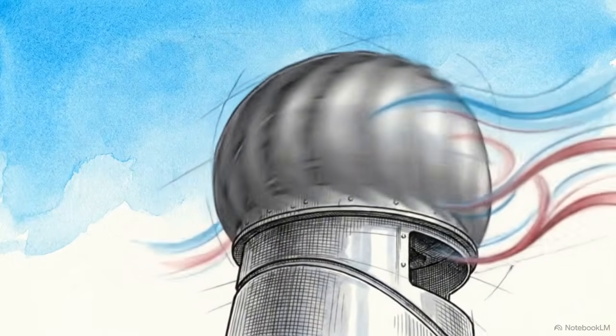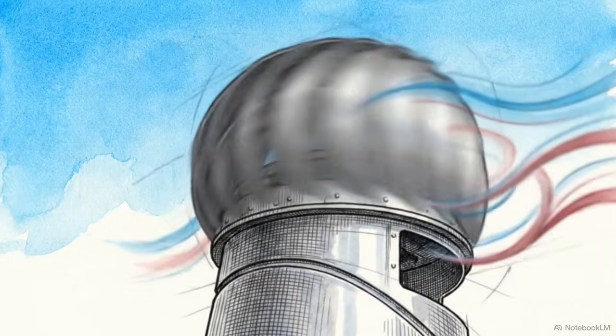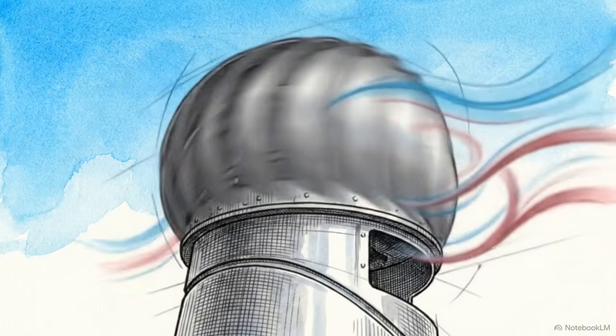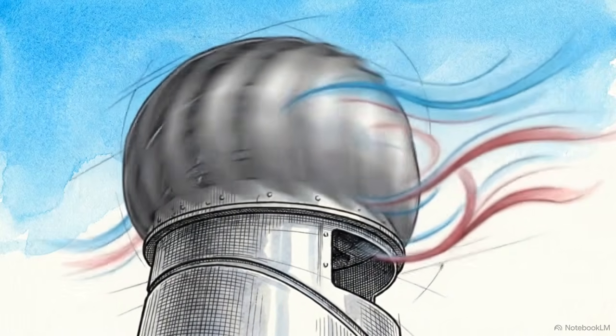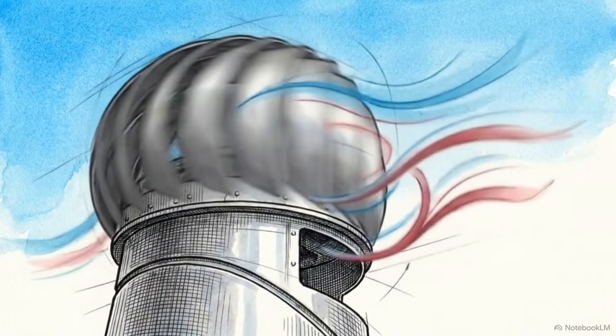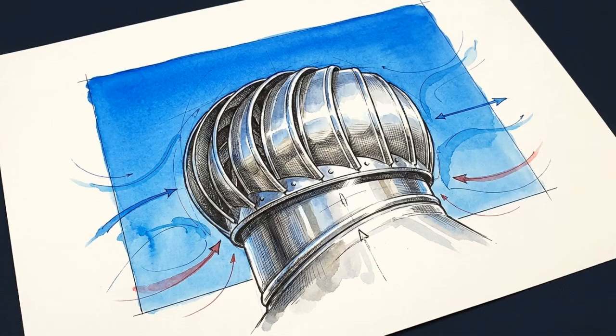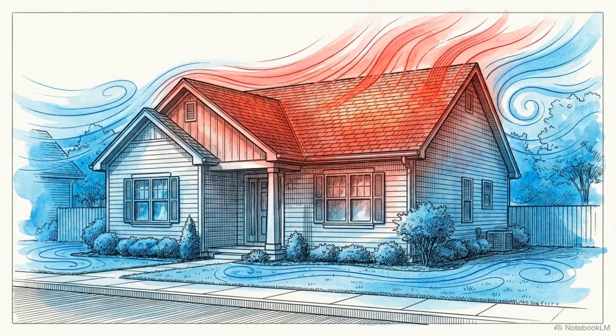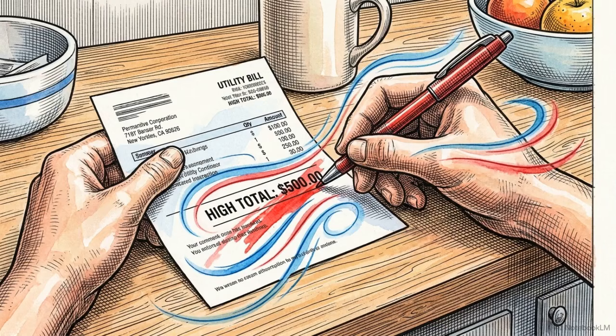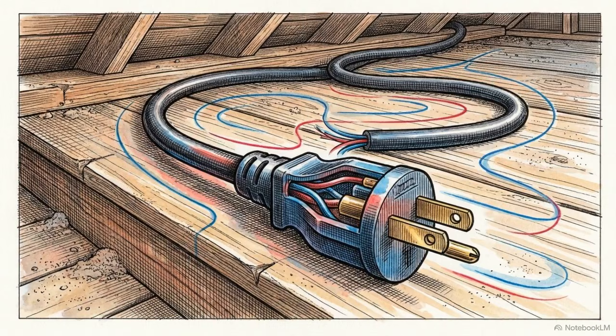Go back just a few decades, and you'd find these spinning metal domes on warehouses, barns, and residential rooftops across the United States and Australia. They're called turbine ventilators, or whirlybirds. Independent testing has proven that these unpowered spinning vents can drop peak attic temperatures by as much as 37 degrees Fahrenheit. That translates to cutting a home's cooling costs by nearly 15%, all without using a single watt of electricity.